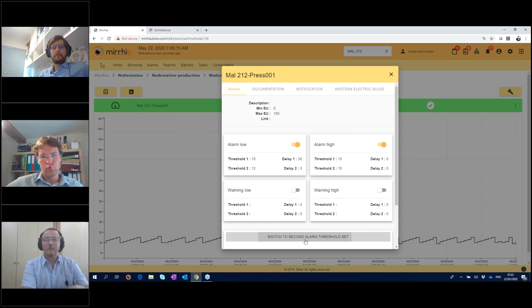This was a question we received prior to the presentation. So if you want an operation mode, like being in production or at rest, and you want to switch from one to the other, it's quite easy. You click on switch to the second alarm threshold set, enter your command, and you switch to the other threshold. You can also tick a box to switch back to the previous threshold at some point in time, to make sure, for instance, that you don't forget to start your monitoring when you're in production. This can be done automatically.